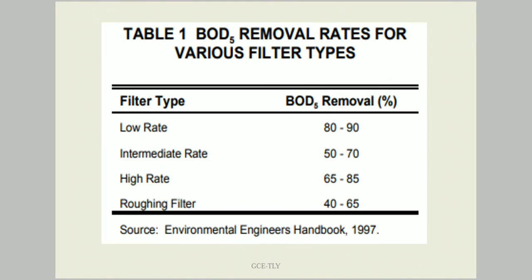Trickling filters can be classified based on rate of filtration as: low rate trickling filter, intermediate rate trickling filter, high rate trickling filter, and roughing filter. The BOD removal for a low rate filter is 80 to 90%, for an intermediate rate filter it is 50 to 70%, for a high rate trickling filter it is 65 to 85%, and for a roughing filter it is around 40 to 65%.